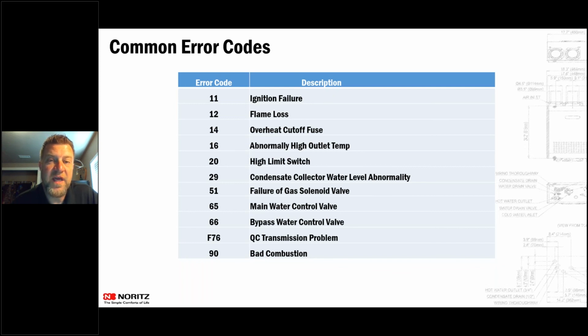So we went out to take a look at it just to see what was going on. And Questar hadn't set the meters yet. So there was no gas going into the 6-plex. If you don't have gas, it's going to give you an 11 code too. So just make sure that you have gas, the air lines are bled, all of that for that 11 code. And that's typically what you're going to see on that 11 code.